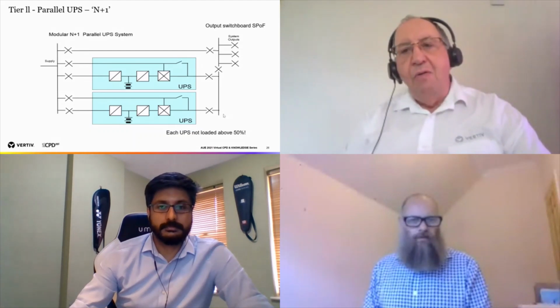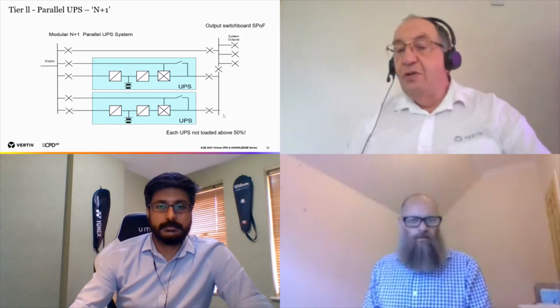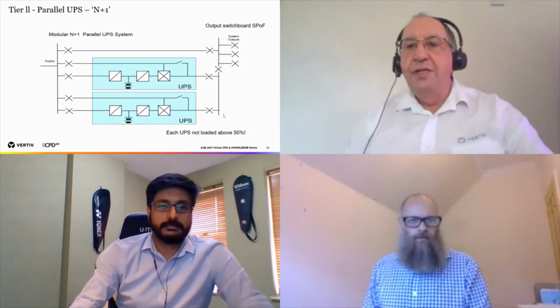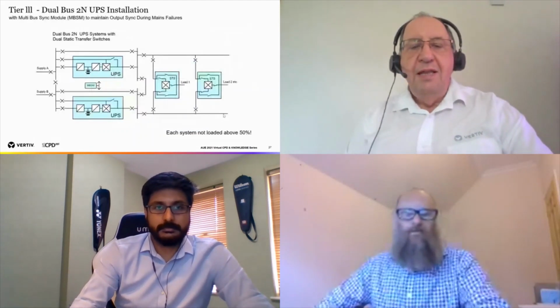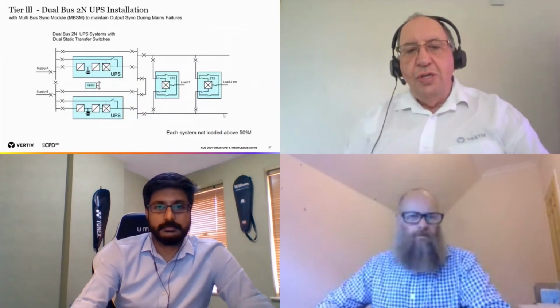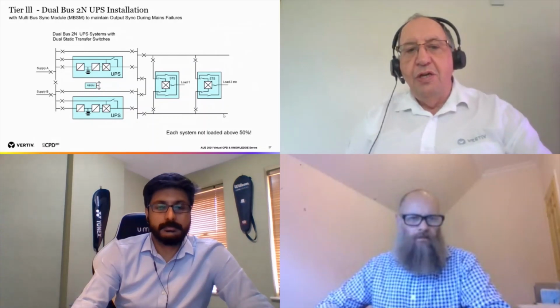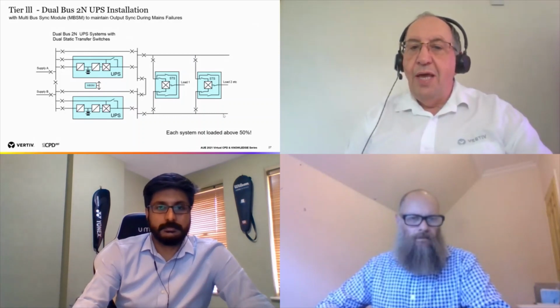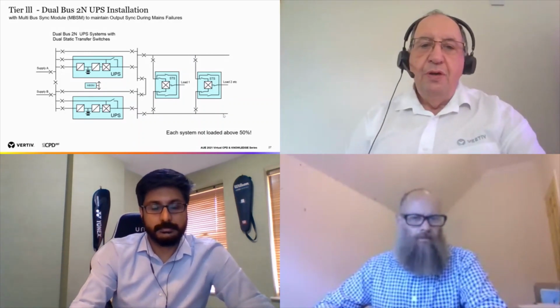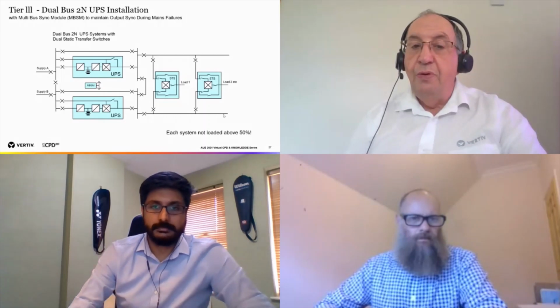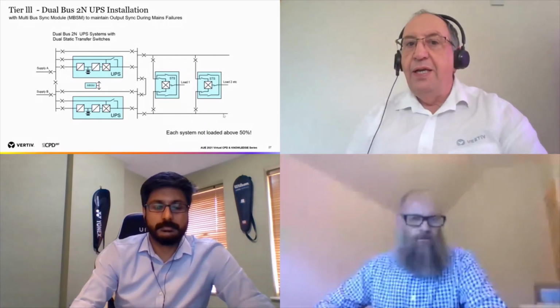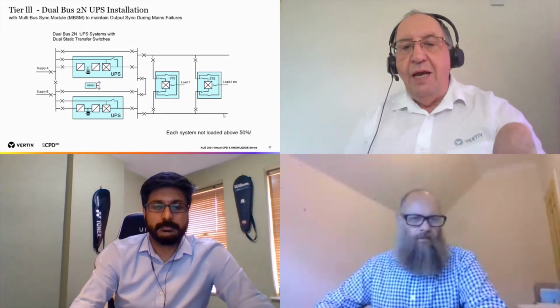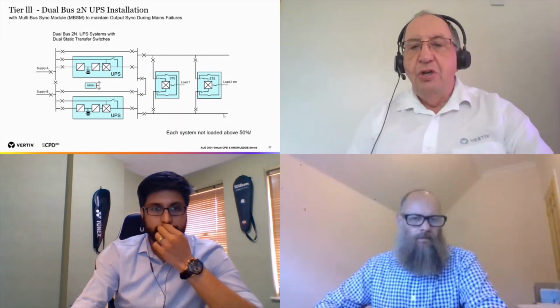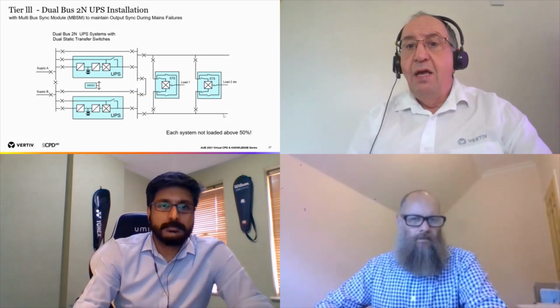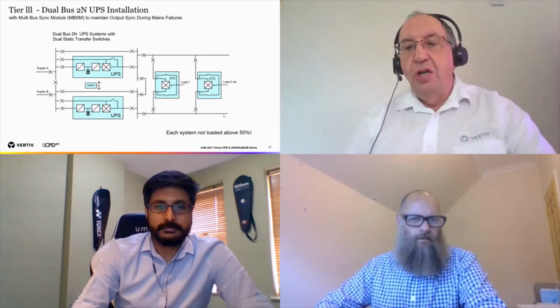But if you note on the output, we've got a common switchboard, so we've still got a single point of failure in that switchboard where it says system outputs. Tier 3, now we've got dual systems supplied by 2 power supplies coming in. So the bottom UPS is supplied by supply B, the top UPS is supplied by supply A. The bus coupler between the output board of UPS A is not coupled to UPS B, but could be if we need to maintain the switchboard. And then downstream, we have an A and a B feed to each static switch, which could be in the server or it could be in the rack. And then we've got the server load being shown as load 1 or load 2.